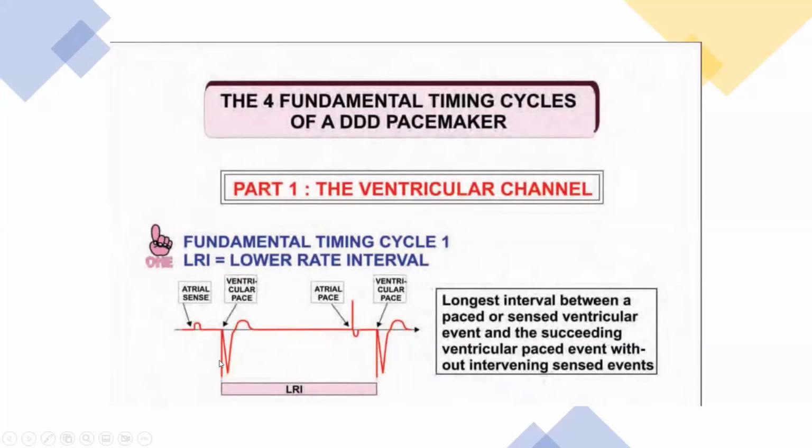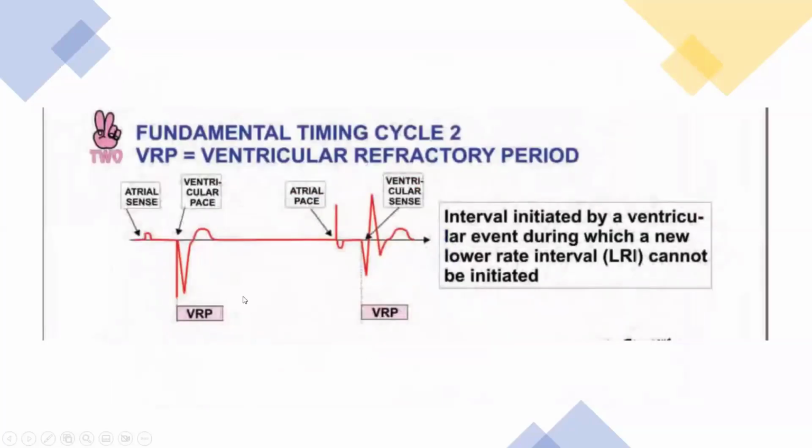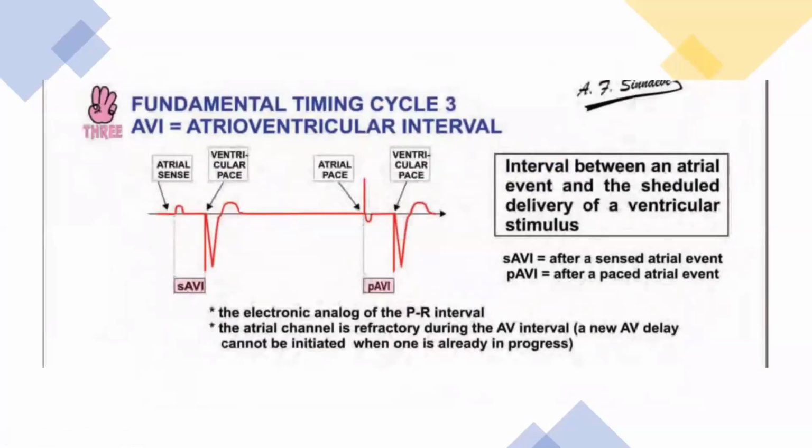So this is the lowest firing of the pacemaker. If the patient is completely dependent on the pacemaker, it will fire the atrial spike, then wait and fire the ventricular spike. The refractory period of the ventricle is the same as we described in the VVI.